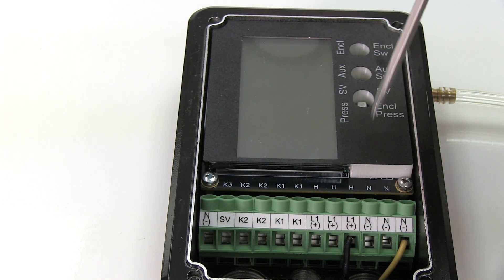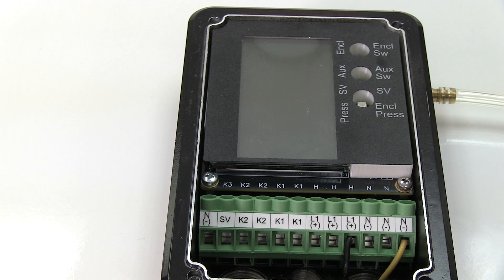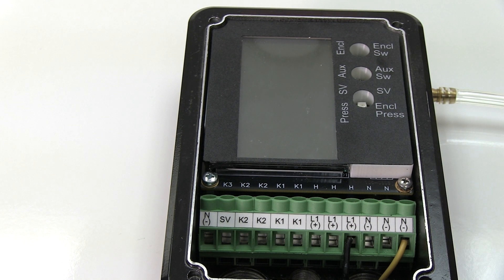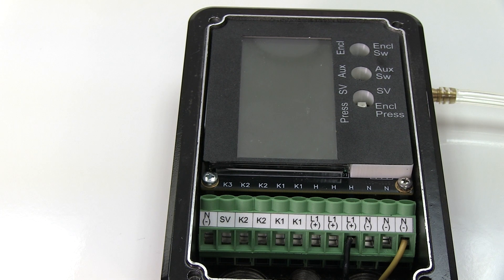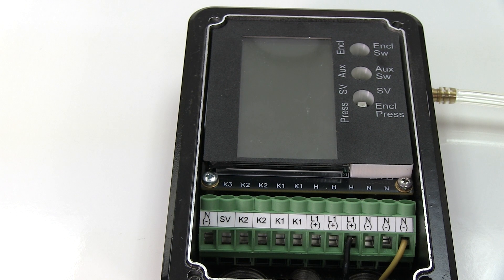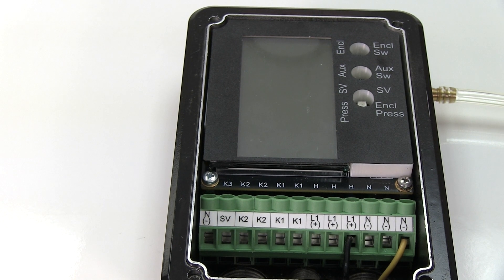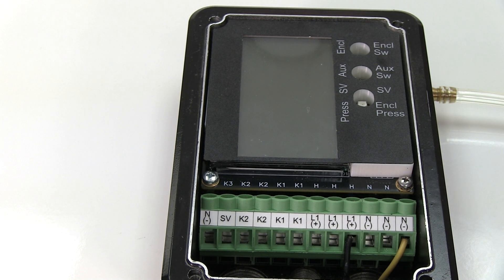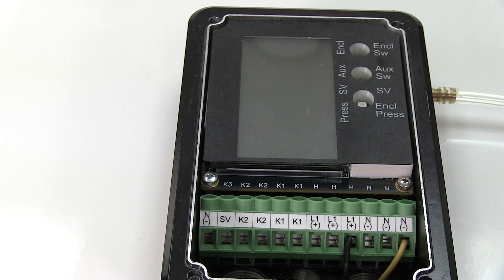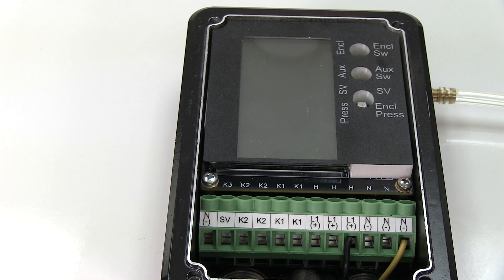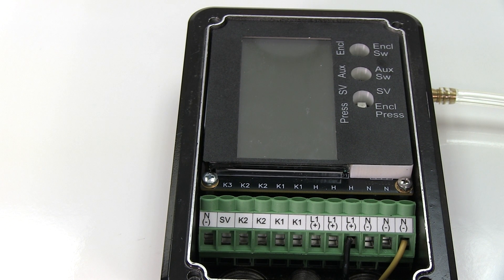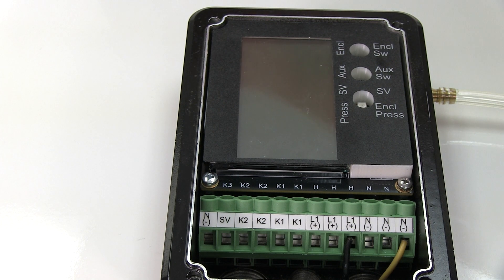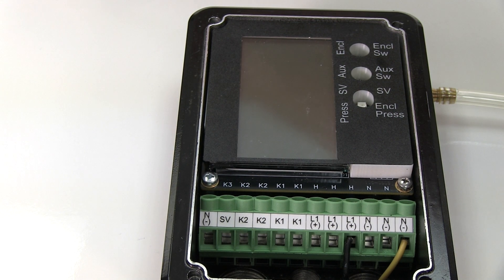Then we have all of our Ns connected on a bus or our neutrals. So the next thing we're going to do now that I have connected power to my unit is wire up the solenoid valve. The solenoid valve has two black wires on it. They're polarity independent, so you can connect either black wire to the SV or the N terminals.